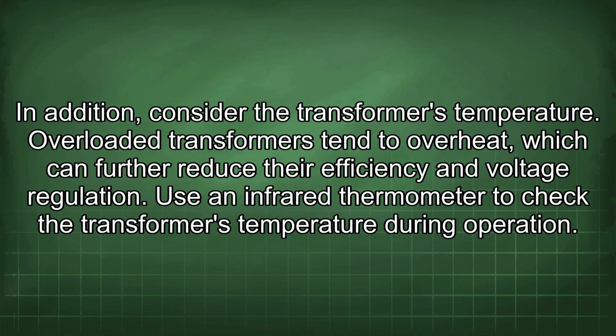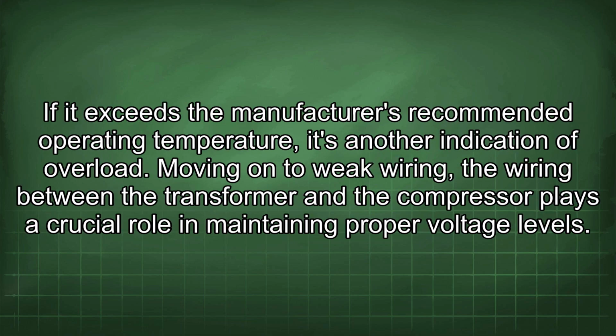In addition, consider the transformer's temperature. Overloaded transformers tend to overheat, which can further reduce their efficiency and voltage regulation. Use an infrared thermometer to check the transformer's temperature during operation. If it exceeds the manufacturer's recommended operating temperature, it's another indication of overload.